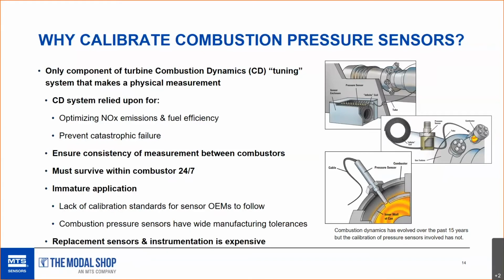And it started with infinite coil, which is the picture at the top of the slide. The sensors were located pretty far from the heat of the gas turbine, and as the sensors got closer, they were developed to withstand higher temperatures, and the frequency response got better. And now the pressure diaphragm is right inside the combustor on most designs, and we have sensors able to withstand these extreme high temperatures, as you see in the picture at the very bottom of the slide, with the diaphragm of the transducer right there inside the combustor. The one thing that has not evolved is calibration.